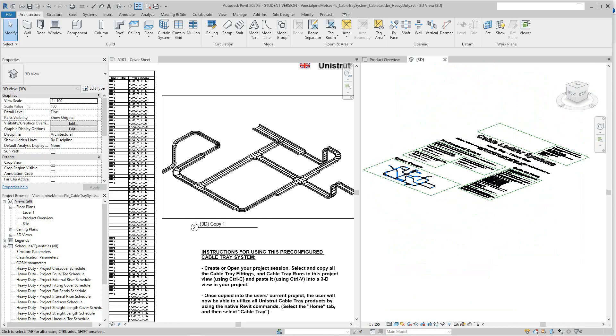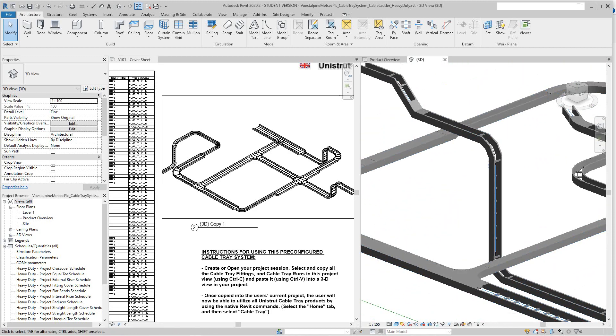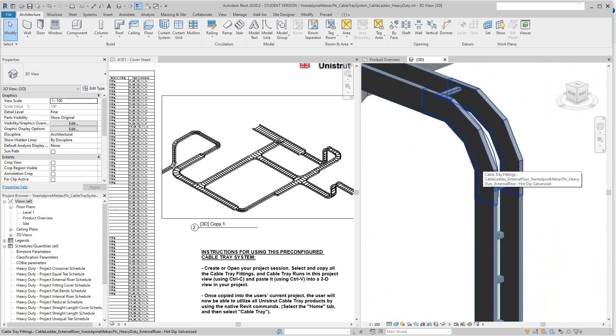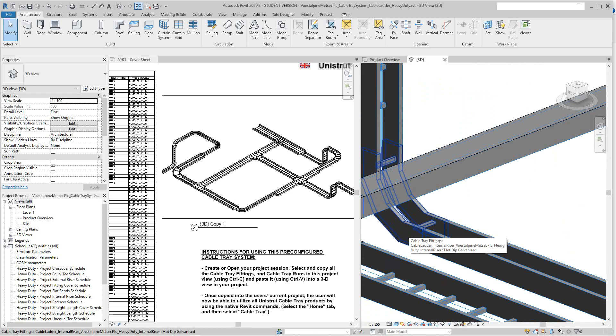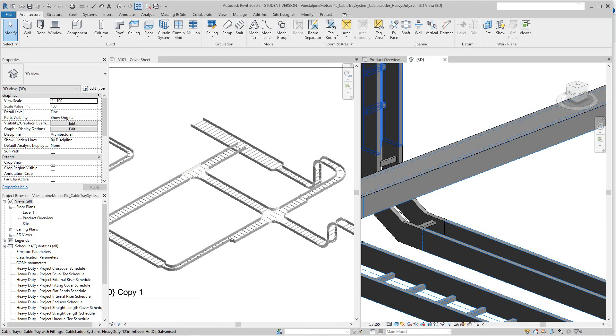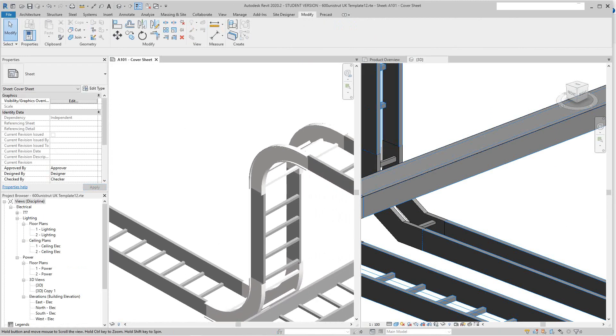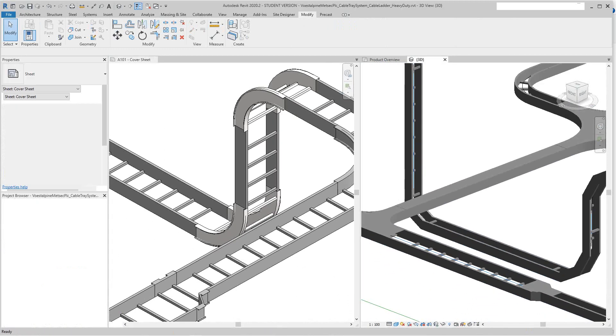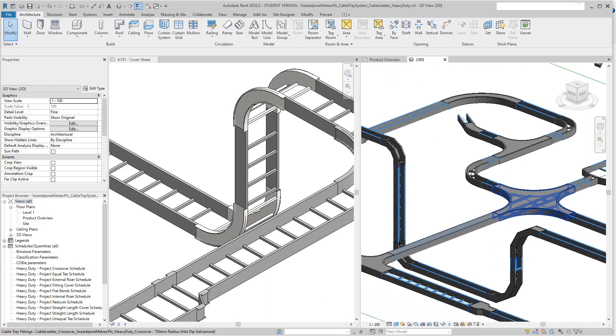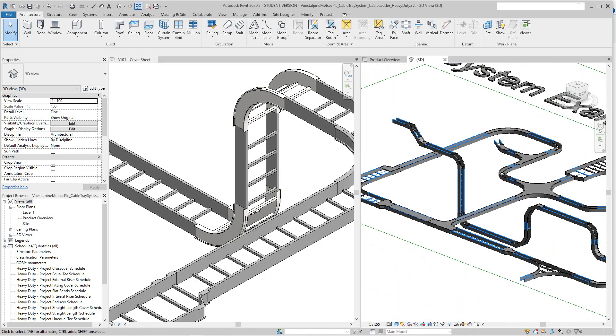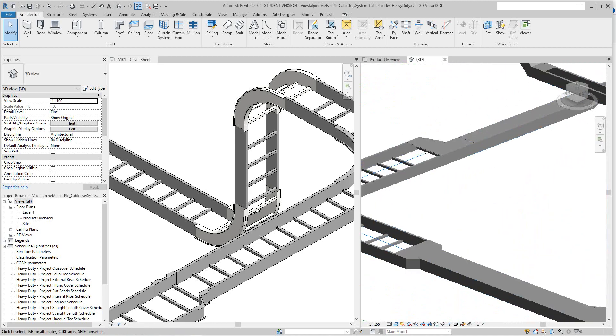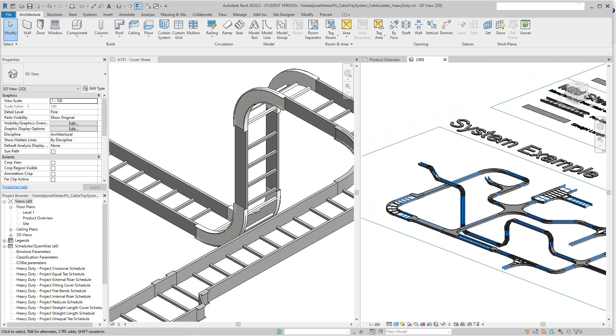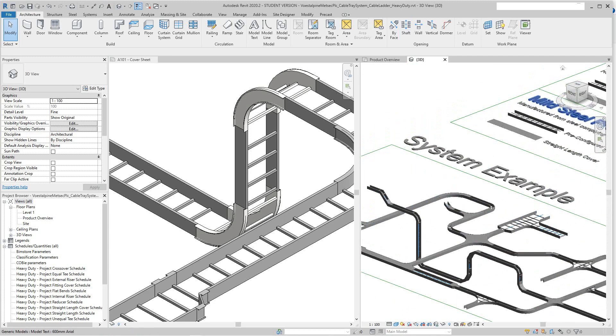Here's their 3D view of their cable runs. Now these cable tray fittings — that's not right, and that's not right. This is the correct way to do it: this is a vertical inside, you see how it runs; this is outside and this is inside. These are not running the right way in this template.